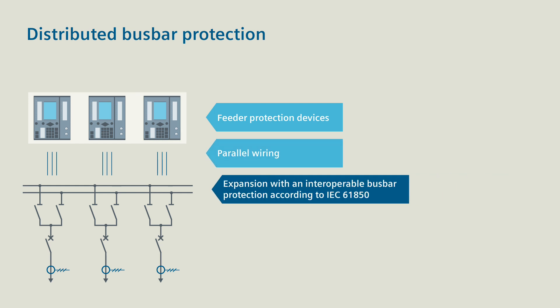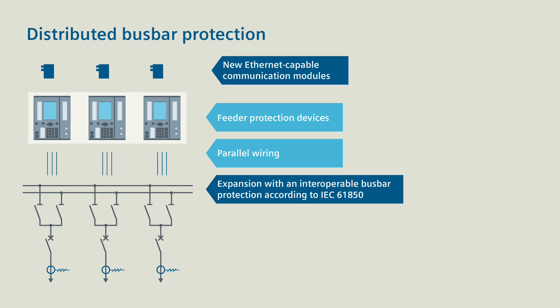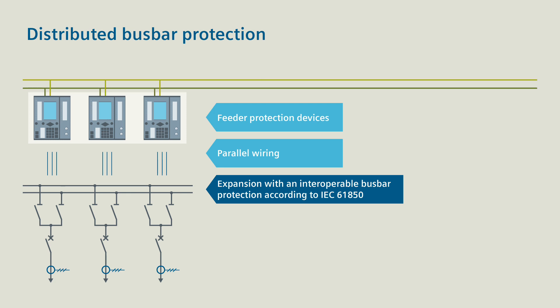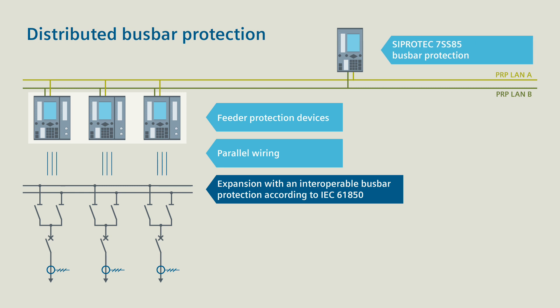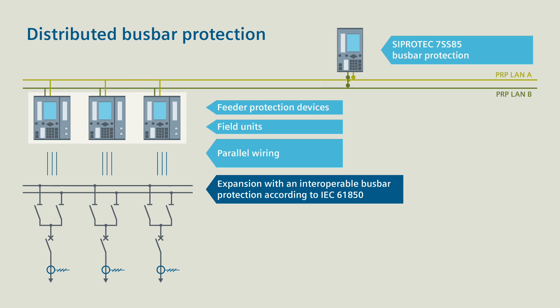For the expansion with an interoperable bus bar protection according to IEC 61850, you only need one of our new Ethernet-capable communication modules for each protection device. You link these via a redundant PRP LAN and connect a SIPROTEC 7SS85 bus bar protection to it. After a brief disconnection, the feeder protection devices also function as field units of the bus bar protection and deliver all necessary process data to the SIPROTEC 7SS85 via the PRP LAN.